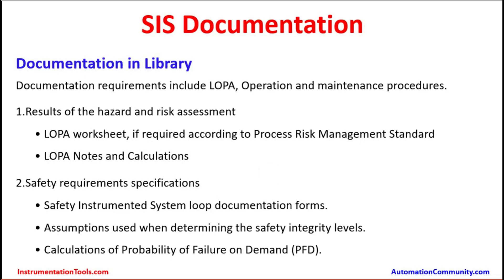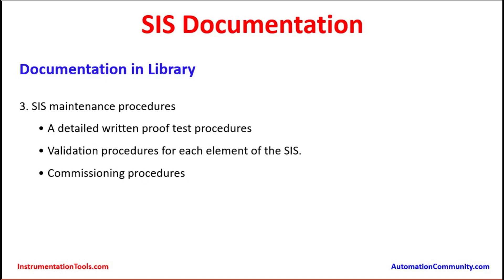LOPA notes and calculations are needed when calculating the probability of failure on demand and safety integrity level. There will be some assumptions since every scenario and every plant condition cannot be physically reproduced, so there could be some risk measurement requirements, and those must be documented. Other required documents include: safety requirements specifications, safety instrumented system loop documentation forms, assumptions used when determining safety integrity levels, and calculations of probability of failure on demand. These calculations are based on the plant's SIS installation and are done at the beginning of a project or when additional SIS facilities are being built. SIS maintenance procedures are also required.